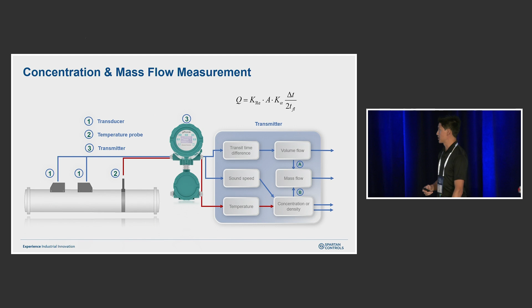Another common question I typically get is, what kind of accuracy can we expect from a clamp-on ultrasonic? The number we typically go by is 1%, with some caveats. If the piping is non-uniform, say fiberglass pipe where the thickness is not consistent all the way, that's going to affect the accuracy. But generally speaking, we'll do a sizing to know what that number is, and we can get pretty close to 1%, which is information we'll provide to you.